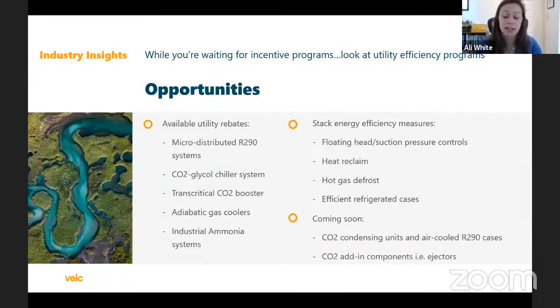Adiabatic gas coolers, again, can be tied in conjunction with CO2 systems to float that head pressure and control to wet bulb temperatures year round, which in certain climates can lead to significant energy savings over even floating according to dry bulb temperatures. CO2 is great for heat reclaim as well if you're working with a utility that offers rebates both for electricity and thermal energy reduction. Hot gas defrost and efficient refrigerated cases. Again, the electronic expansion valves inherently included with case controllers result in energy savings that can be calculated.